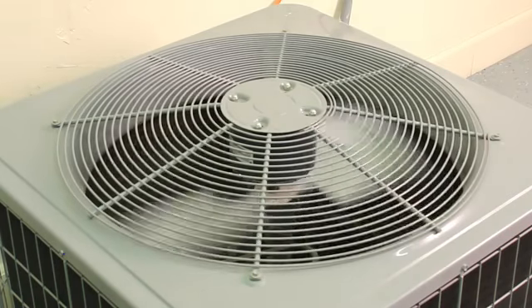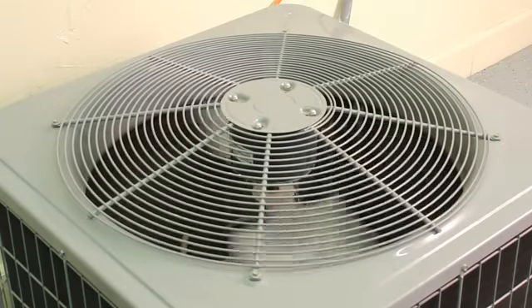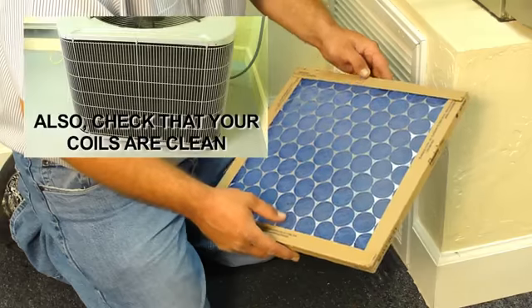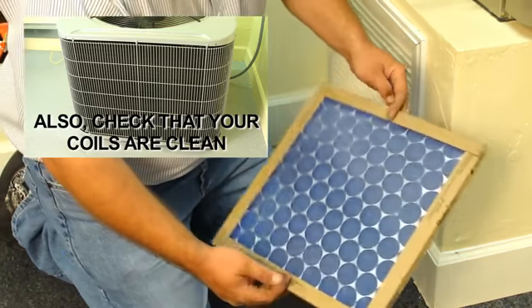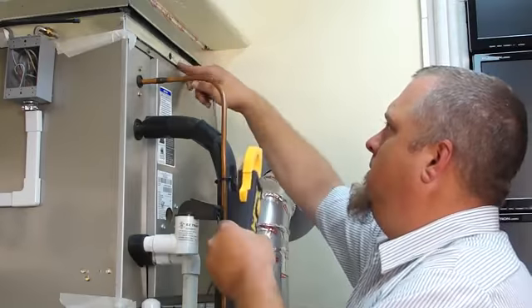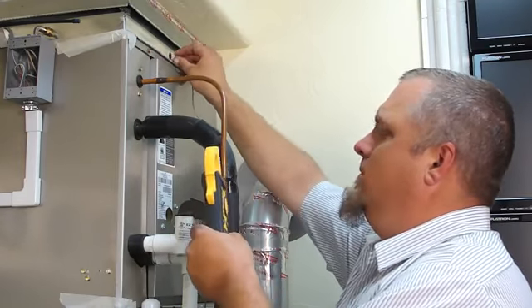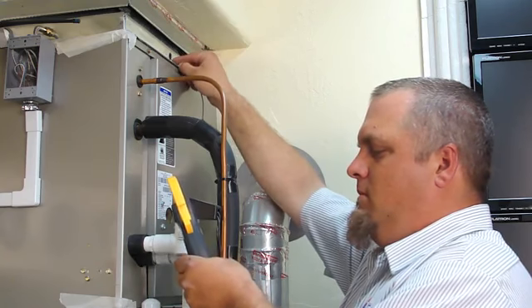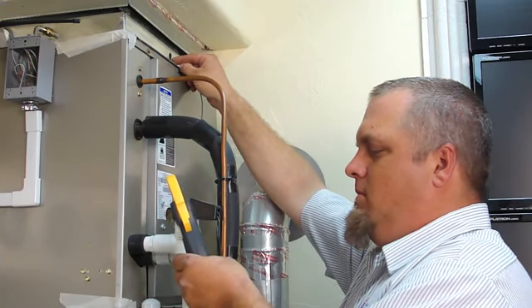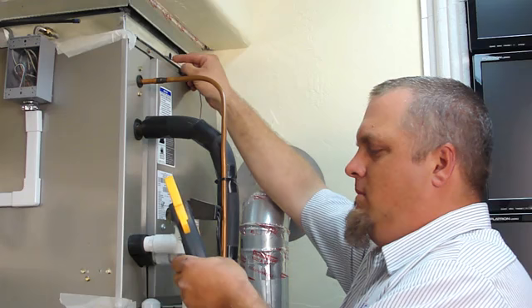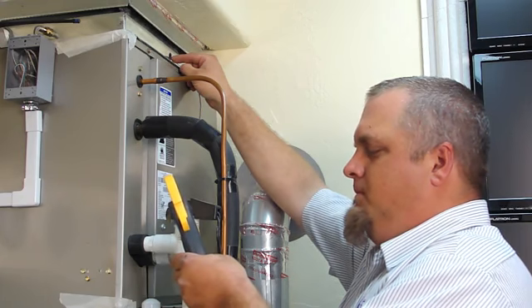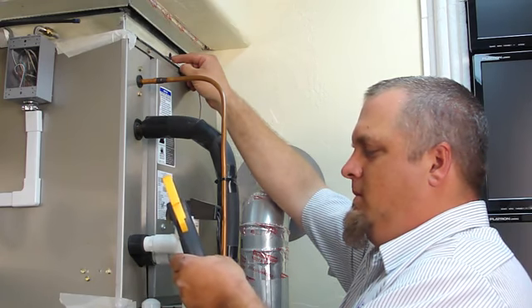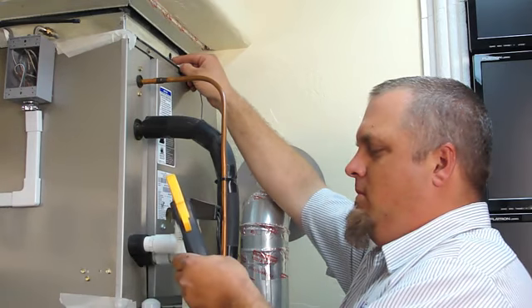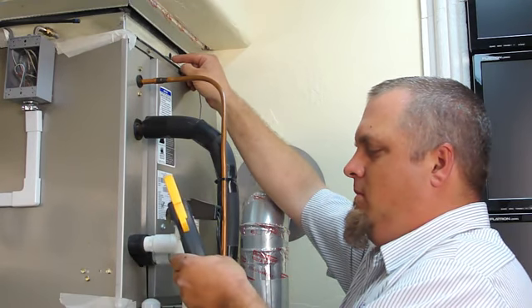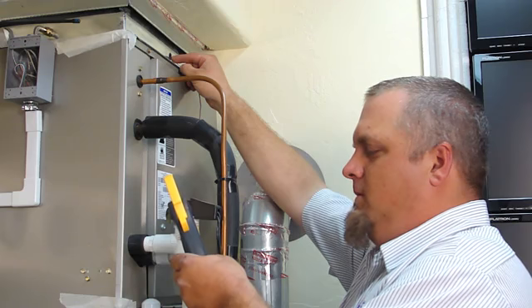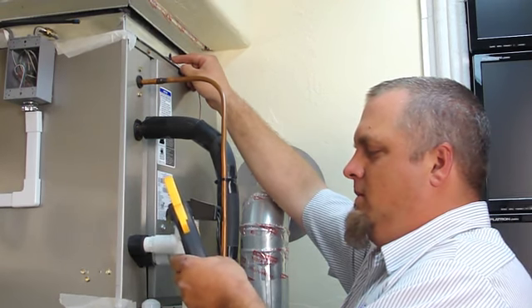Listen for the unit to cycle on and off as it reaches that set point temperature. Also be sure to check that your filters are clean and change them if they are not. In cooling mode, check that the supply temp at the indoor evaporator coil is at or below 55 degrees Fahrenheit. In straight AC units with a furnace and/or heat strips, temperature should be taken at the supply plenum. For a heat pump or a straight cool system without a heating source, the temperature should be taken at the supply side of the indoor evaporator coil.